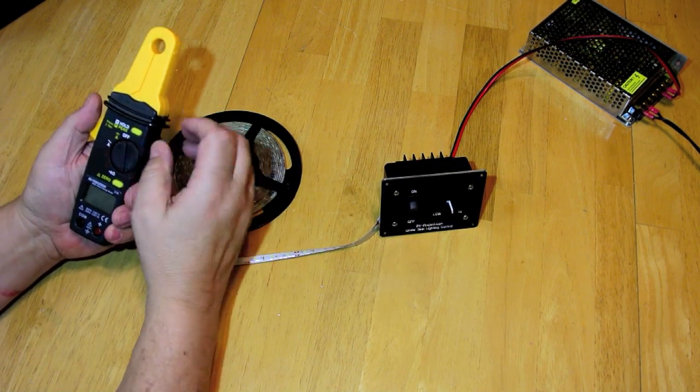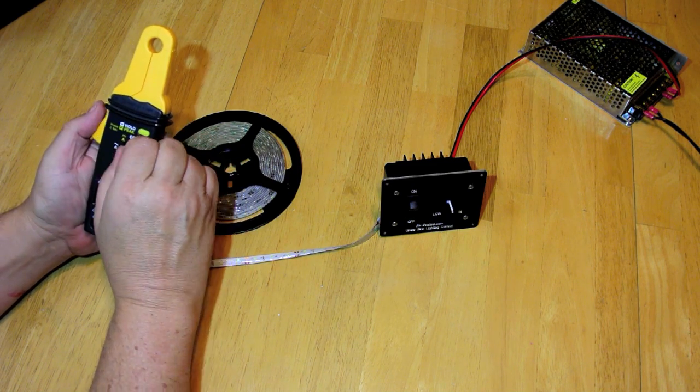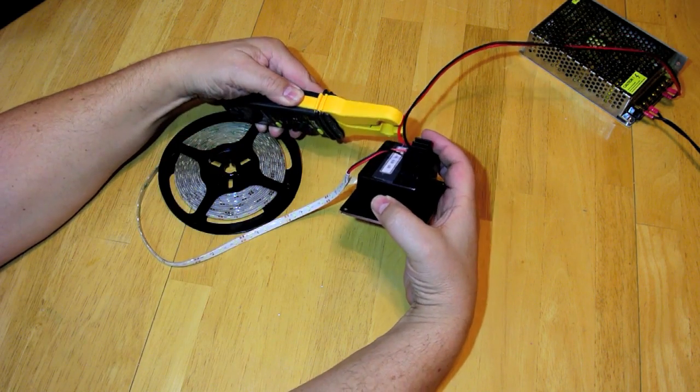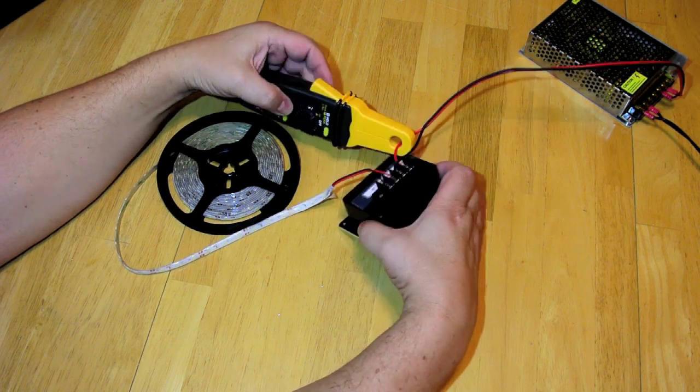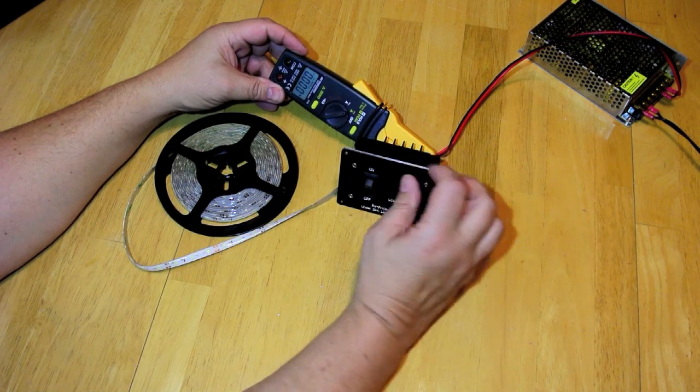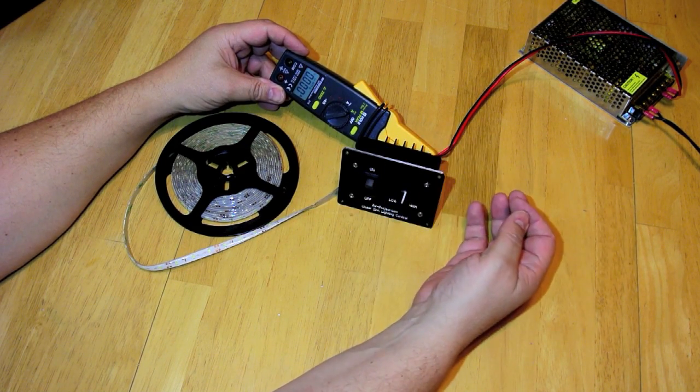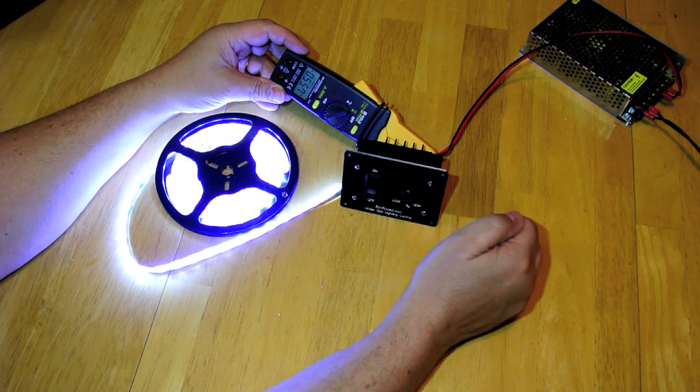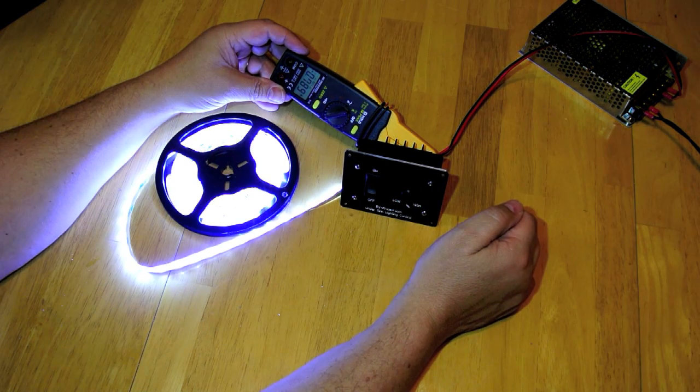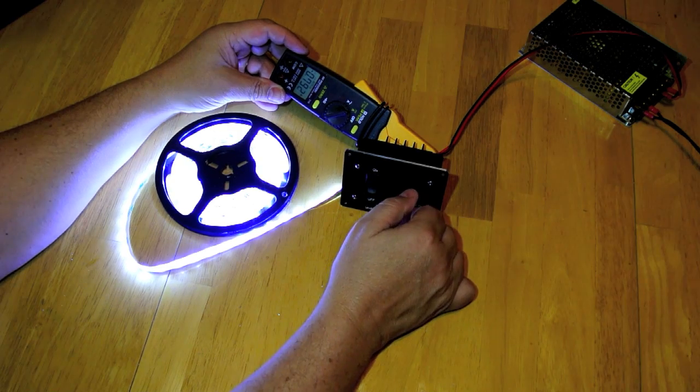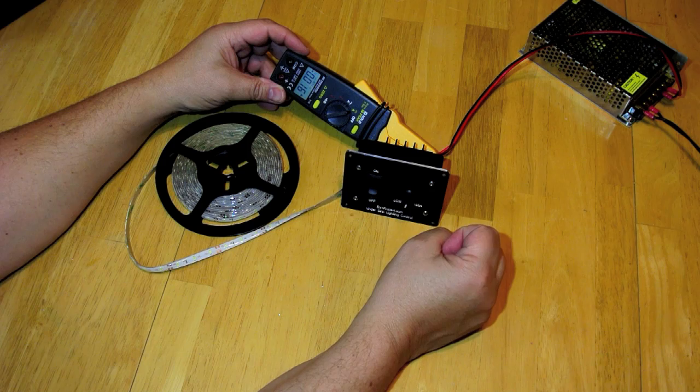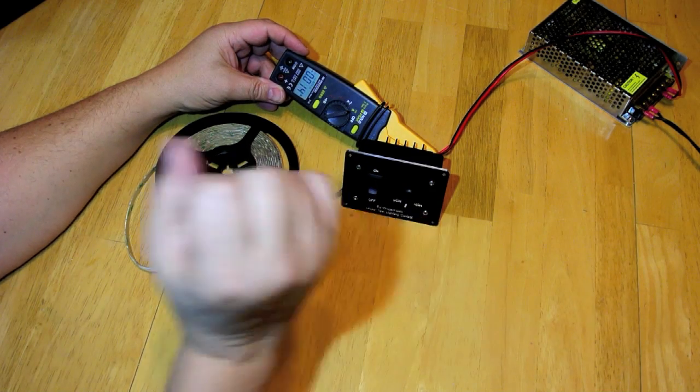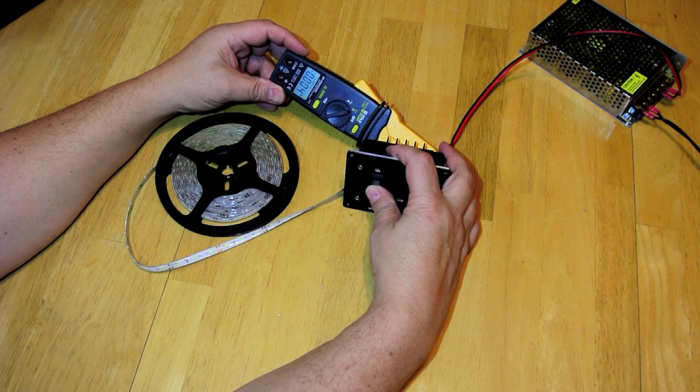Now we're going to measure to see how much residual current we have here. Put this clamp meter on the positive side. We have zero current which means that's fine because it's off. We turn it on at full blast, we have almost 800 mA of current. But then the significant part is when we turn it off, we have 15 mA of current. Turn the switch off and it goes down to zero.